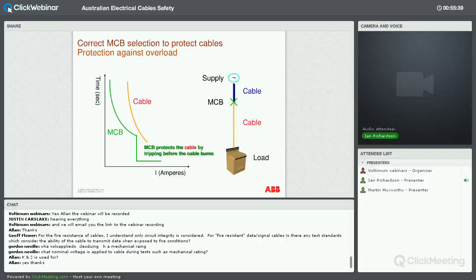So we want to make sure that our breaker protects the cable by tripping well before we get to this threatening value of the cable. And as I mentioned, this is not a reflection on the cable itself, because if we get to this value, we're asking the cable to do something which it's actually not designed to do. So we need to protect it correctly, choose the correct circuit protection to make sure that the cable is able to do its job.